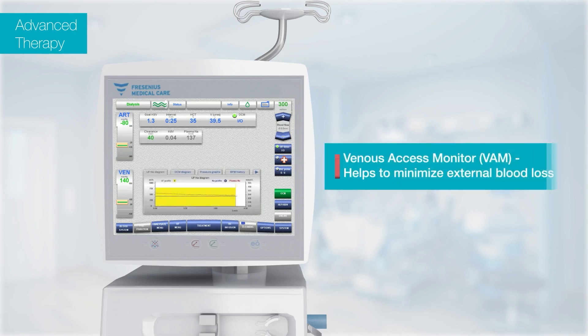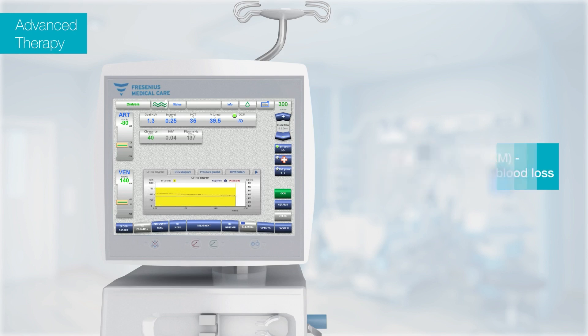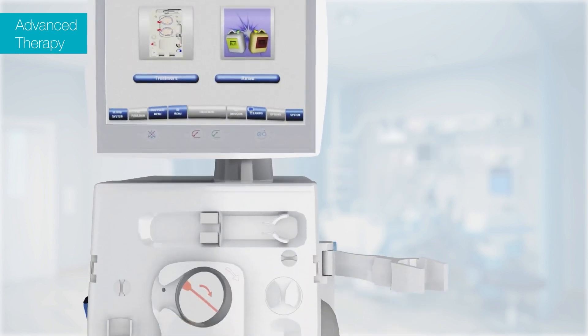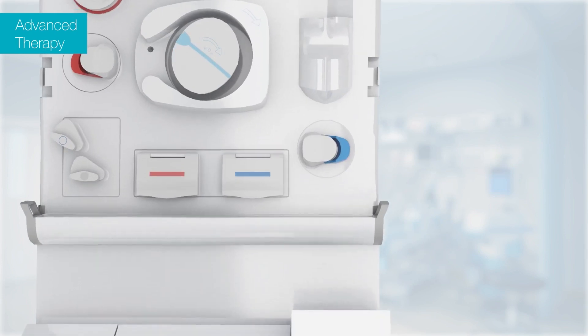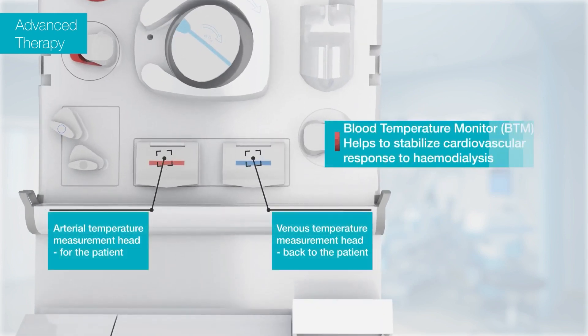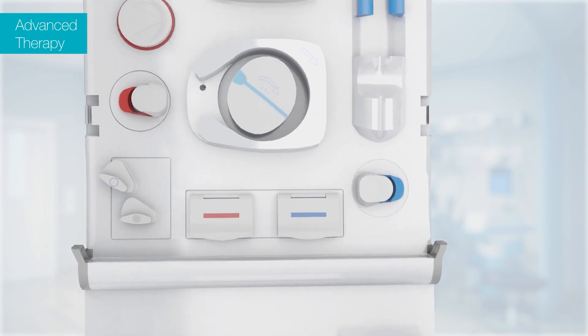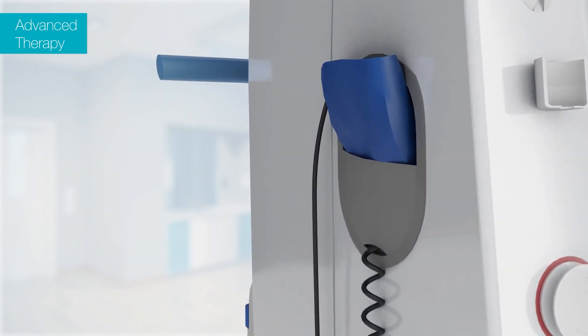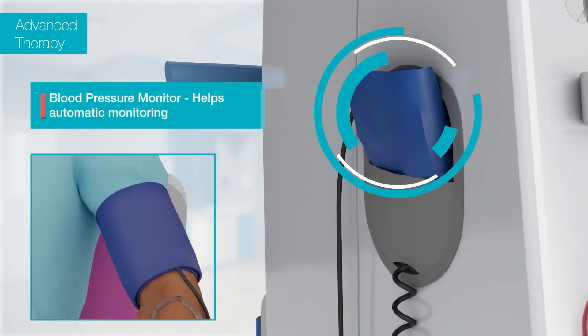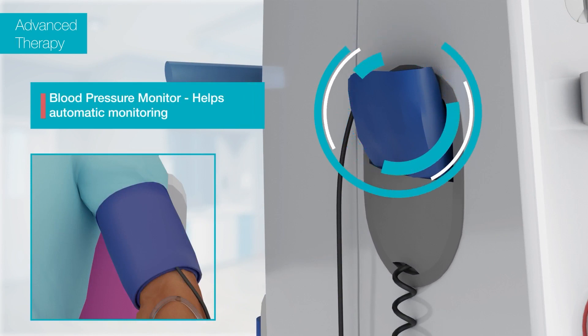The venous access monitor helps in minimizing the risk of external blood loss. The blood temperature monitor helps in stabilizing the cardiovascular response to haemodialysis and ultrafiltration. The blood pressure monitor automatically monitors blood pressure during dialysis.